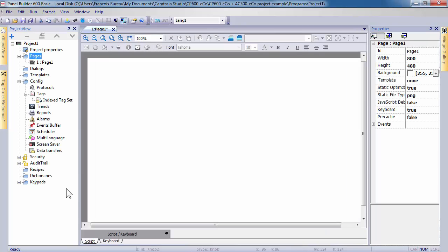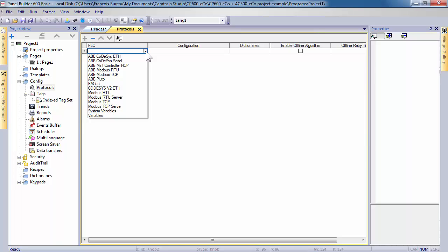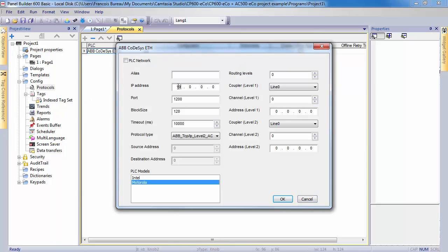The white page displayed corresponds to your working area. And on the left side, you can discover all the elements of your project in project view. We will now select a protocol. This is the first step before creating anything else. Double-click on it to open the window parameters. Click on plus to access the selection of all device drivers available with CP600 EcoPanels. In the drop-down list, select the desired protocol, ABB CoDeSys ETH driver, to be able to work directly with AC500 Eco variables configured in the symbol file.